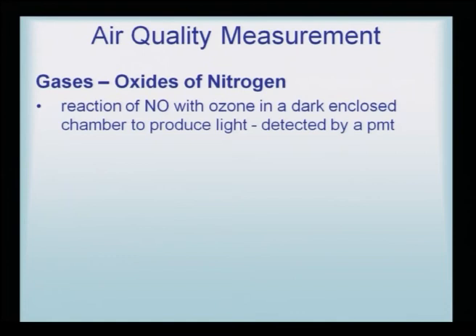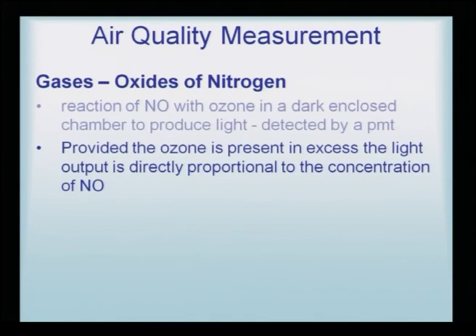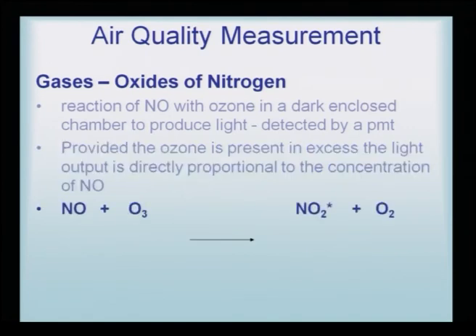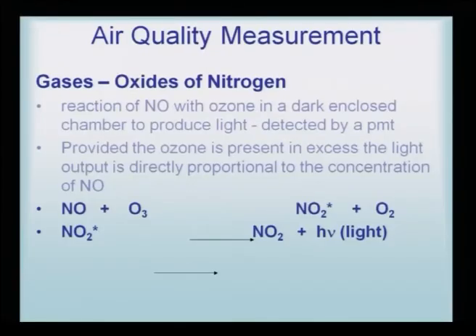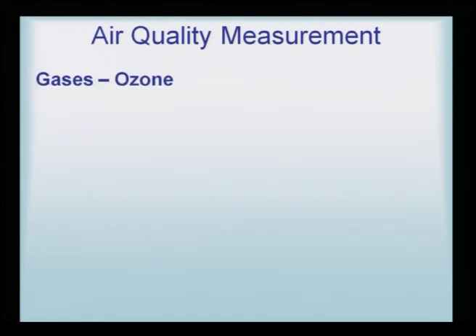For gaseous samples of nitrogen, the reaction of NO with ozone takes place in a dark closed chamber to produce light, and that is detected by a PMT. Provided the ozone is present in excess, the light output is directly proportional to the concentration of the NO. So, this is how the reaction takes place. NO and ozone react and NO2* is generated, and it then forms NO2 and emits light. So, this is how the NOx are analyzed.